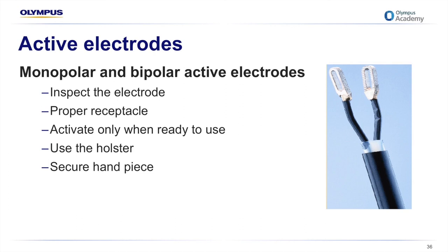Activate the electrode only when ready to use. Always place the active electrode into an insulated holster when not in use. If the active electrode should fall off the sterile field and down the side of the OR table, ask to disconnect it immediately to prevent accidental activation or related risks. Always clean the active electrode to prevent char buildup on the active electrode tip and accessories. Don't activate it if flammable vapours such as those from alcohol prep solution are present.